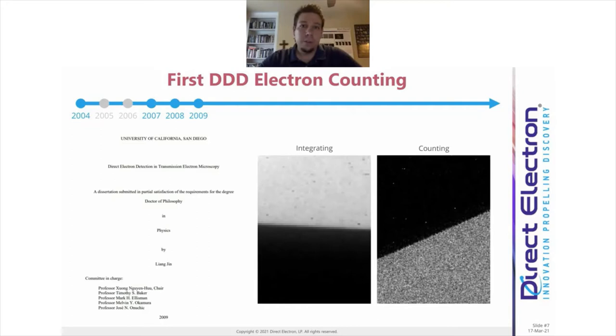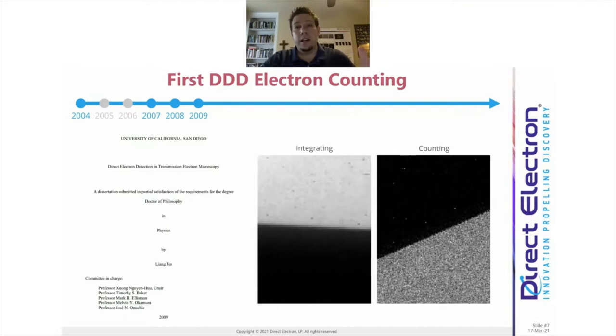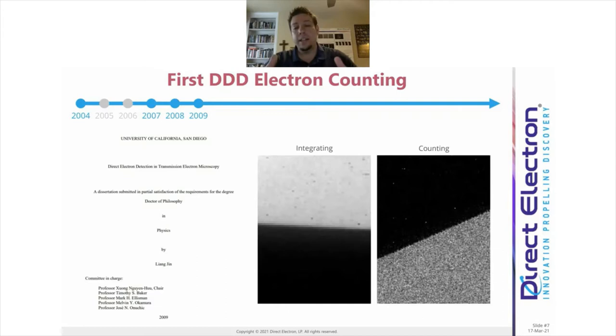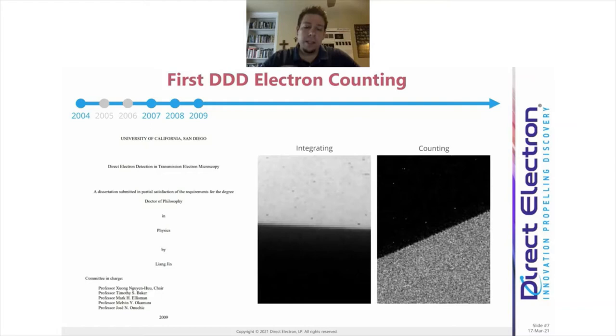In 2009, the method of electron counting using these detectors was published both by UC San Diego and by a paper from the MRC LMB with Greg McMullen, showing that you could identify single electron events on this camera. Because these direct detectors are so sensitive, you can see individual events hitting the detector, and in software you can normalize the energy of each event and localize them to a single pixel — counting electrons instead of just measuring total energy deposited.